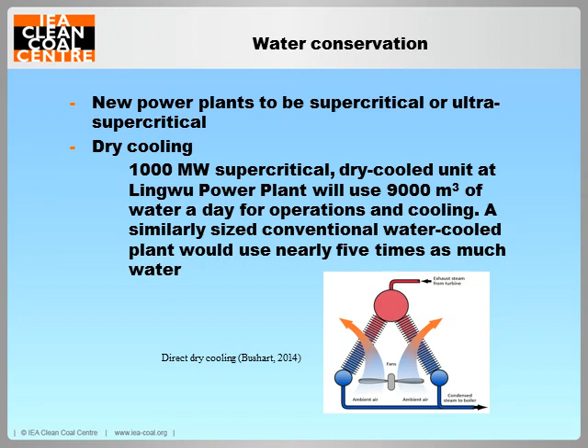To give you some idea of the water savings involved, the 1,000 megawatt supercritical dry-cooled unit at the Lingwu power plant will use about 9,000 cubic metres of water a day, whereas a similar-sized conventional water-cooled plant would use nearly 3 times as much water. So the Chinese government is prepared to accept the lower thermal efficiency associated with dry cooling.